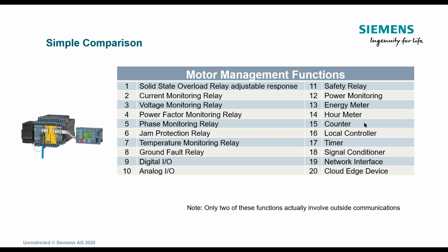For instance, I had a process out in Nevada where that motor shouldn't turn on more than maybe twice a day, and that's it. It was some processed water, and if it got to a certain level, this pump would turn on and take it down. If it turned on more than 2 times a day, there was something significantly wrong upstream of that process. So we put in a counter for that motor, and it sent a message to the operator saying, this pump has turned on twice in the last hour. Please send somebody out to check on what's going on. And so he was able to use that again as a process measurement and verification that everything's going well with the process.